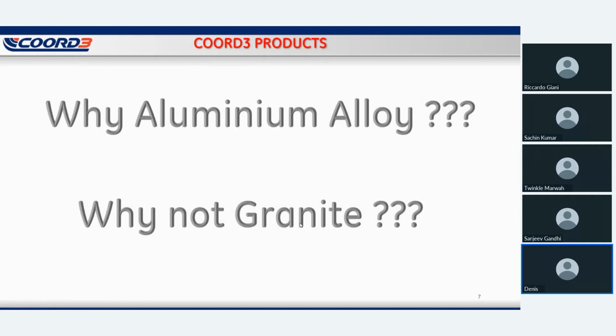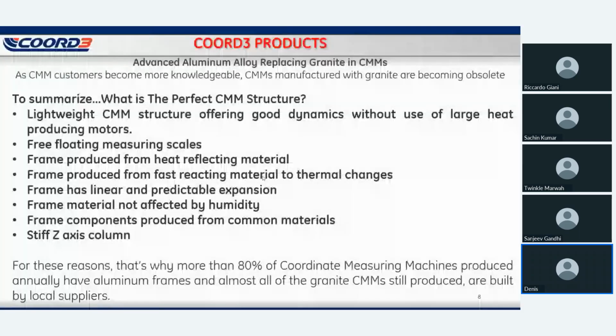So let me introduce the difference between aluminium and granite, because our CMMs are made totally in aluminum alloy. We prefer to use aluminium because it is a lightweight structure, offering good dynamics without the use of large heat-producing motors. We use the free-floating measuring scale, so our scales on the machine are not glued for the total length of the axis, but are only fixed in one point. So the scale is free to move.